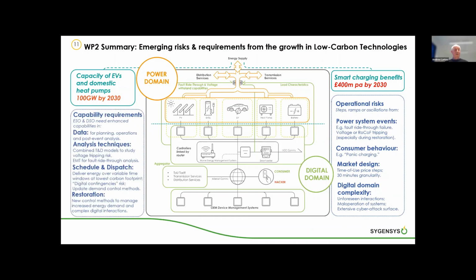In terms of the grid operator side of things, there are new capability requirements. How do we get data to plan and do post-fault analysis? What sort of analysis techniques do we need to look at the risks of coincident tripping? How can we schedule these resources and control them? And what are the digital contingencies that we may need to consider if any of these systems fail? And then if we have to go through a process of restoration, how will all of these smart loads behave? What is the risk that they all default to full power when they lose communication and we end up with massive cold load pickup?